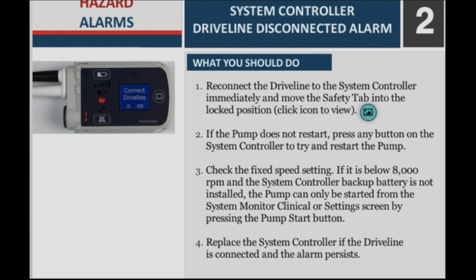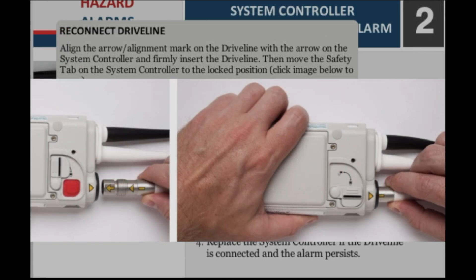Step 2: If the pump does not restart, press any button on the system controller to try and restart the pump. Step 3: Check the fixed speed setting. If it is below 8000 RPM and the system controller backup battery is not installed, the pump can only be started from the system monitor clinical or settings screen by pressing the pump start button. Step 4: Replace the system controller if the driveline is connected and the alarm persists. To reconnect the driveline, align the arrow or alignment mark on the driveline with the arrow on the system controller and firmly insert the driveline. Then move the safety tab on the system controller to the locked position.